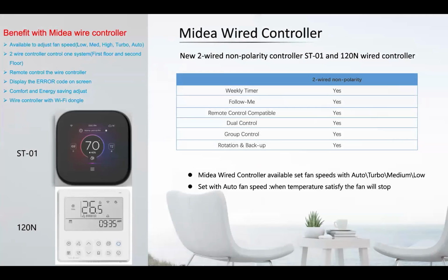All right, so the ST1 and even the 120N, which is the white thermostat, or white control on the bottom, they both have a weekly timer. You have up to 8 program periods per day. As for the follow me function, they are remote control compatible, which means you can use the handheld remote to change the temperature on the thermostat. It's dual control capable. So you can put one system in the house, have a control upstairs and a control downstairs, do individual programming, and it will switch back and forth. Last call will be the one that gets the demand.